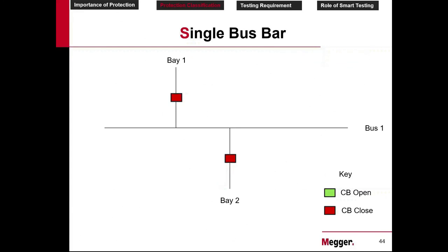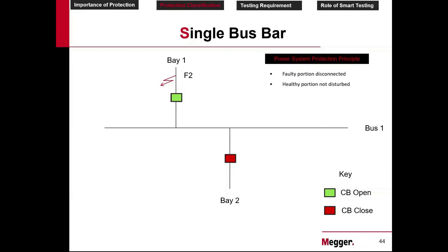Let's see another example. The fault occurs here. Which breaker should we trip? The first one, does it satisfy this principle? Yes, the faulty portion is bay 1 and the healthy portion is bus 1 and bay 2. It's not disturbed. Okay, you may feel that if you open this anyway, there is no current feeding in this bus. So how do we say that the healthy portion is not disturbed?